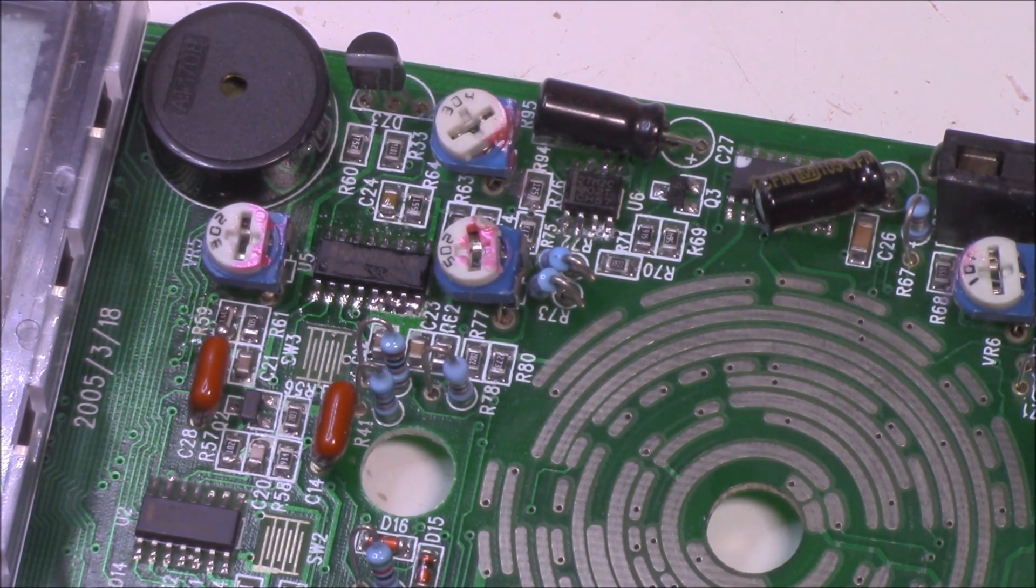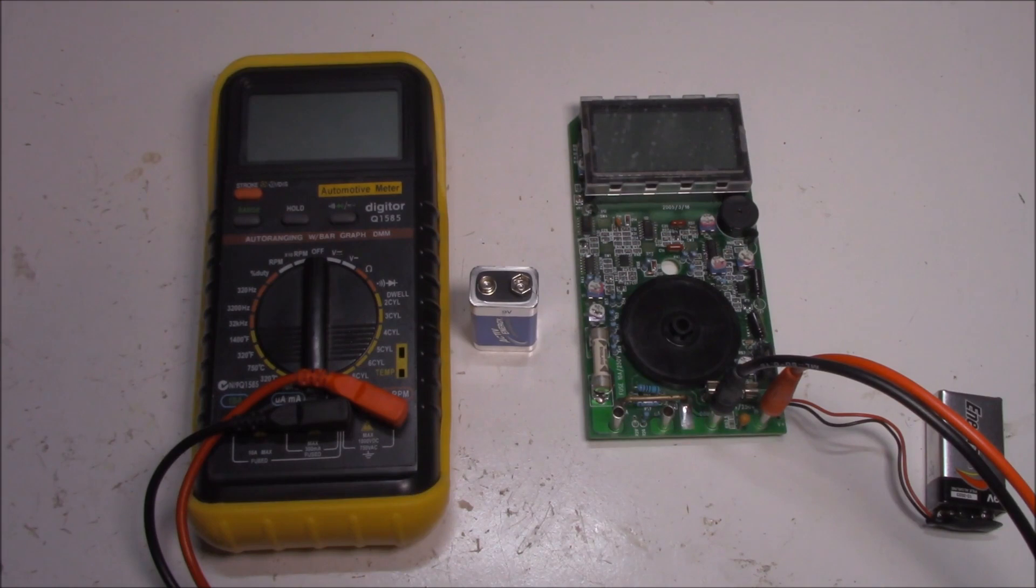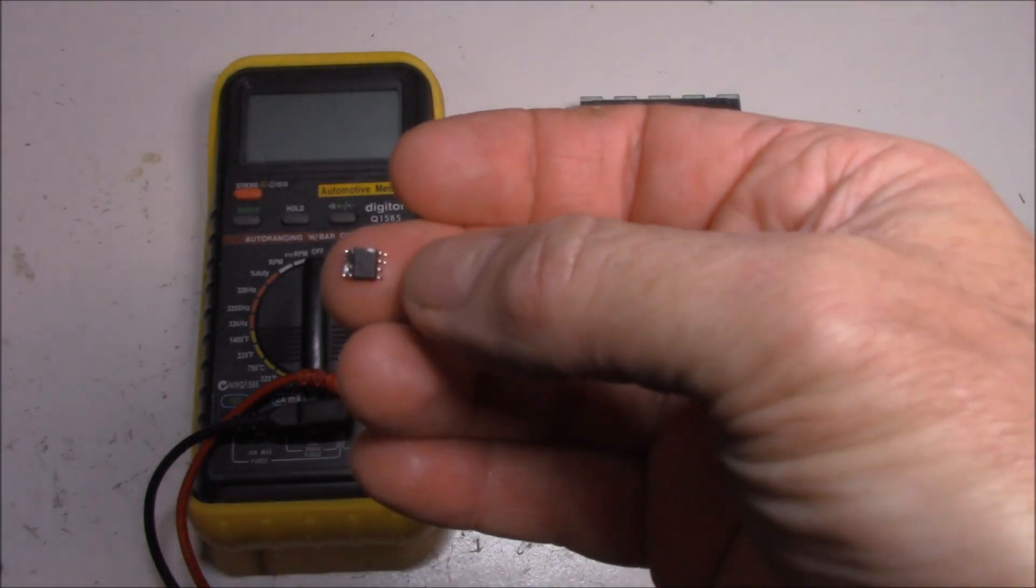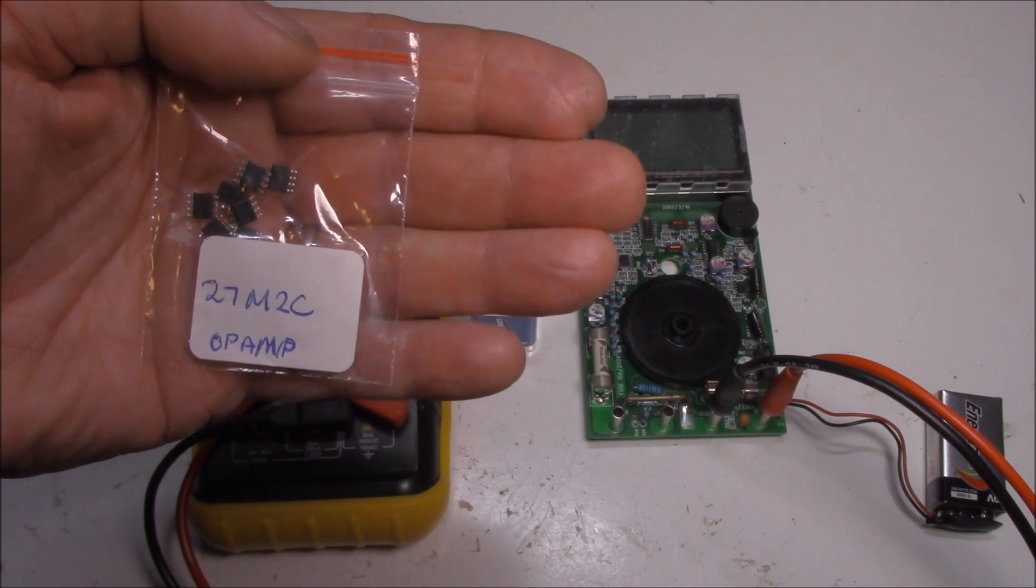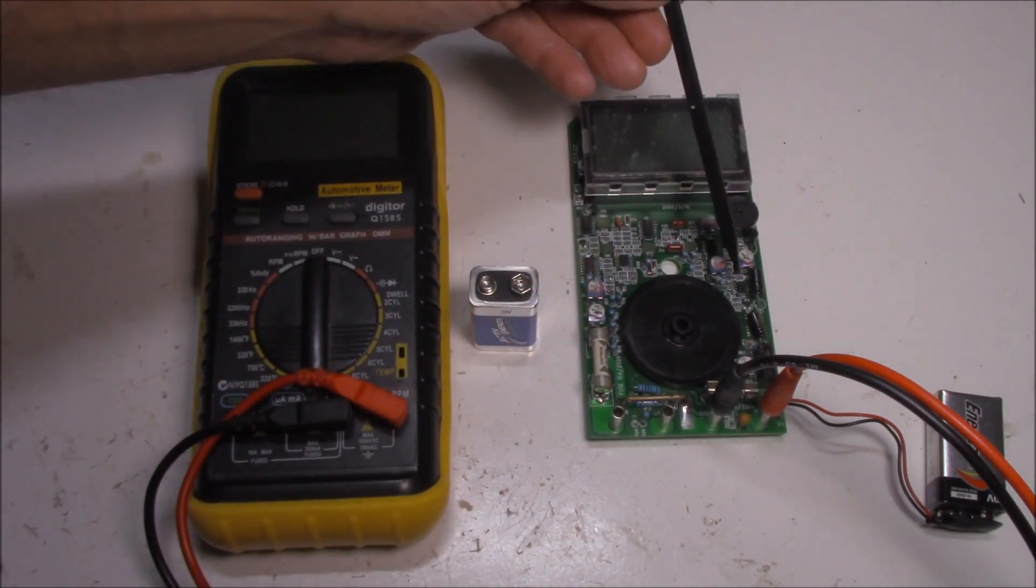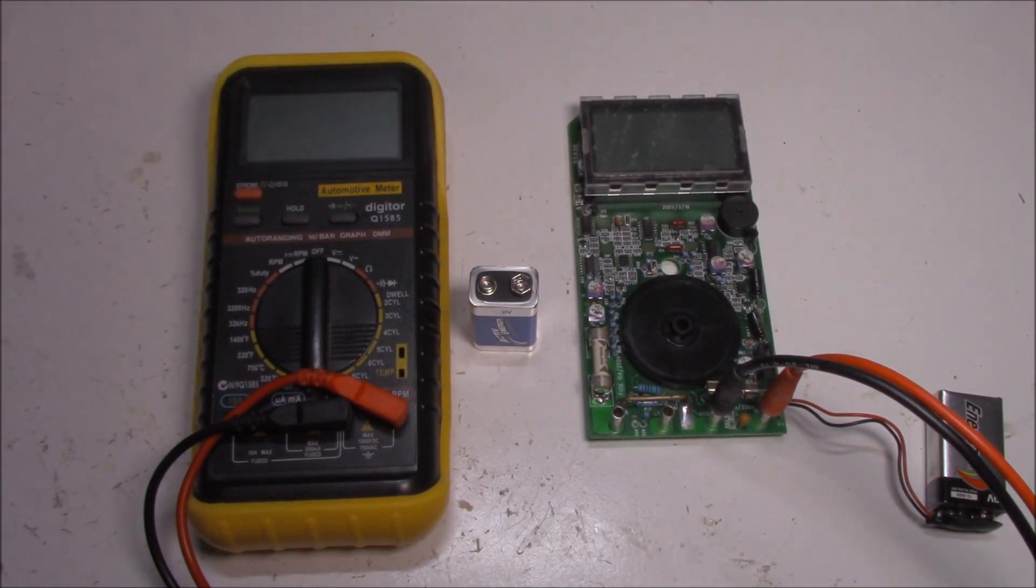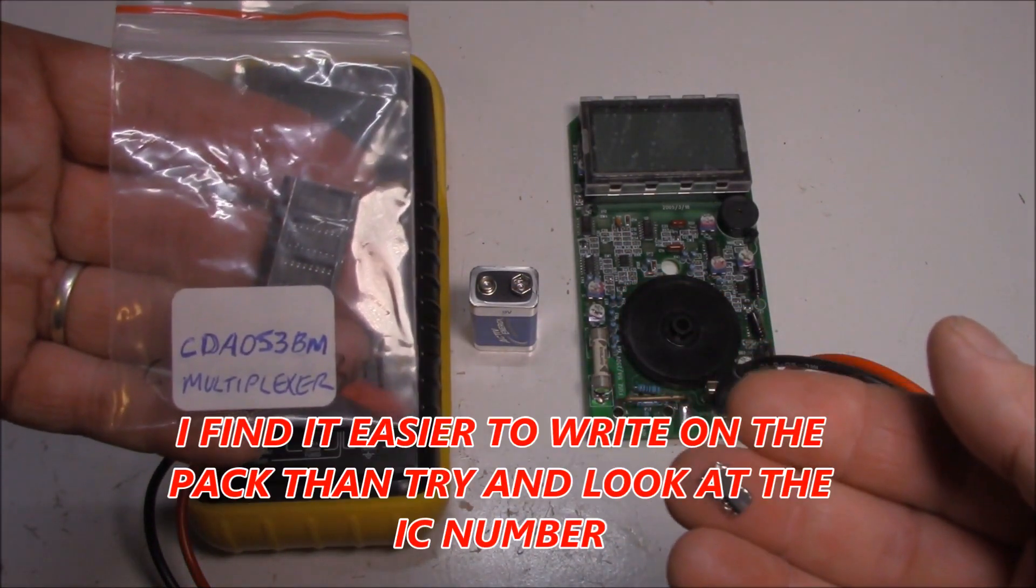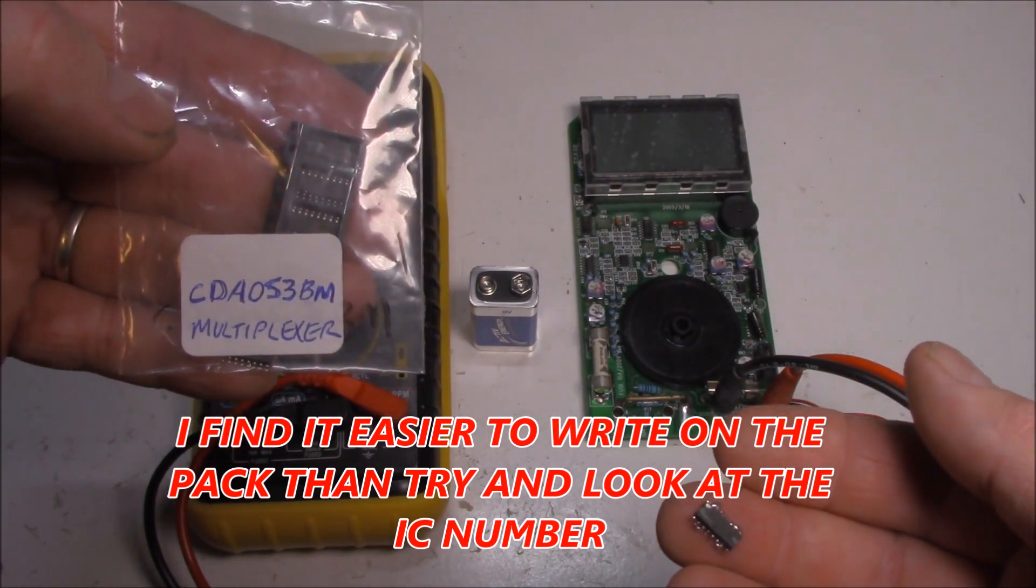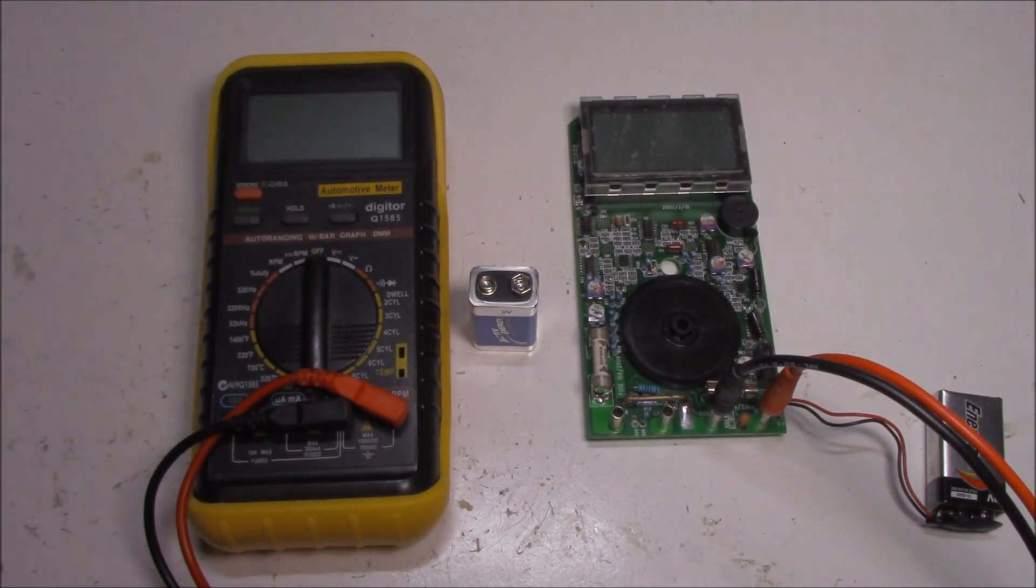I'll double check with a multimeter later on, but for now I'm just replacing all those dodgy ICs. I've gone ahead and just replaced two of the ICs that I suspected were faulty. This little bloke here, which is classified as a 27M2C, which is an op amp, and that was located just over here. The second fellow that I did is classified as a CD4053BM, and that's a multiplexer. And that was located right here. I think I've got it sorted. Check this out.